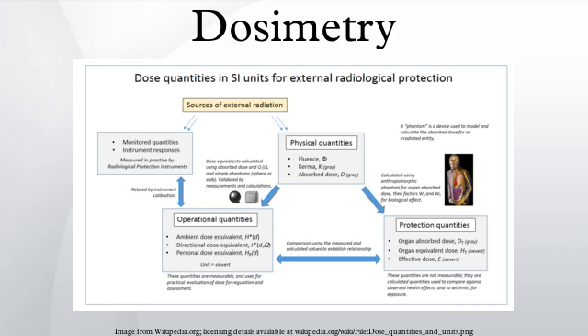The NPL in the UK operates a graphite calorimeter for absolute photon dosimetry. Graphite is used instead of water as its specific heat capacity is one-sixth that of water, and therefore the temperature rises in graphite are six times more than the equivalent in water and measurements are more accurate. Significant problems exist in insulating the graphite from the laboratory in order to measure the tiny temperature changes. A lethal dose of radiation to a human is approximately 10–20 grays, which is 10–20 joules per kilogram. A one-centimeter cubed piece of graphite weighing two grams would therefore absorb around 20–40 millijoules. With a specific heat capacity of around 700 J kg⁻¹ K⁻¹, this equates to a temperature rise of just 20 mK. Dosimeters in radiotherapy are routinely calibrated using ionization chambers or diode technology or gel dosimeters.